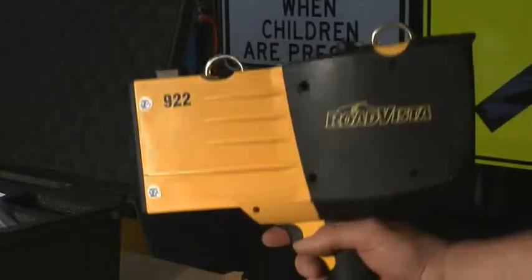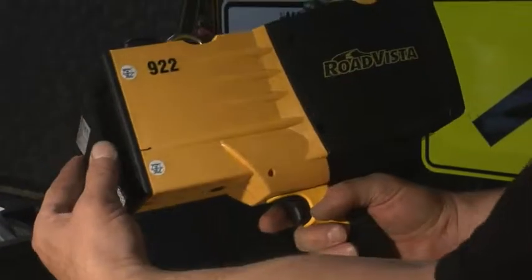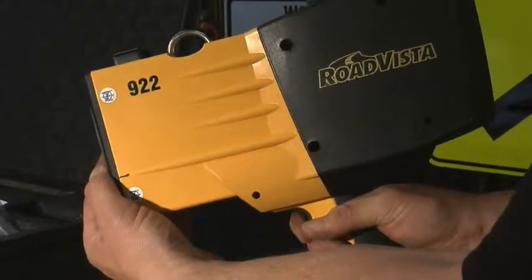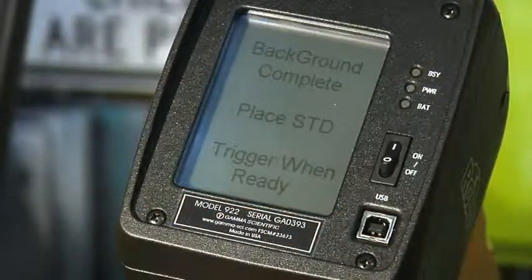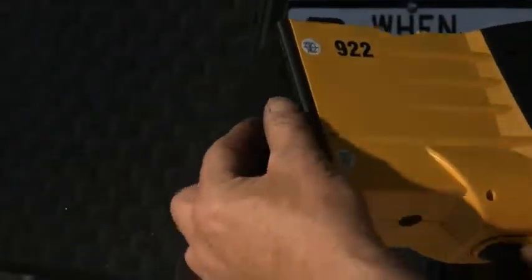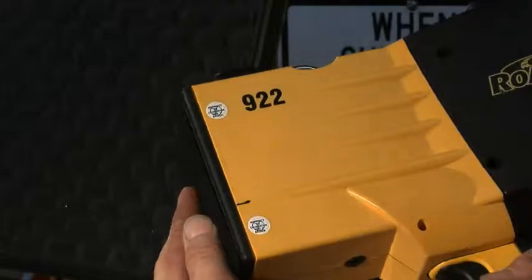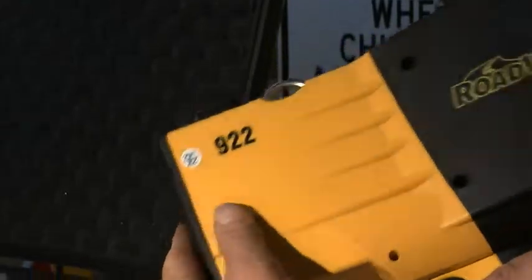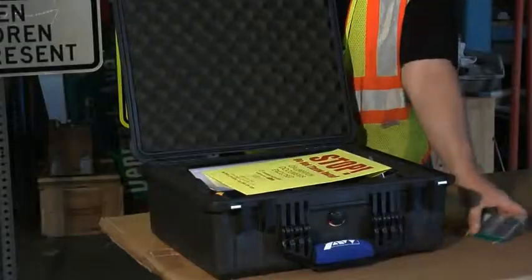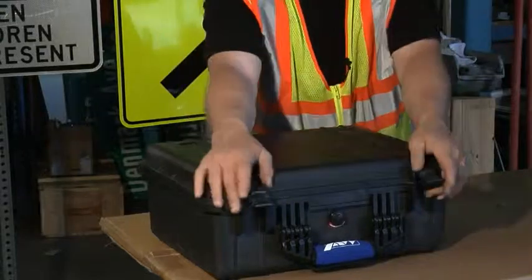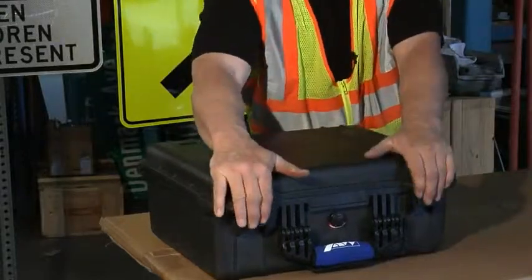Place the black or zero side of the calibration standard card over the trigger until a beep sounds. Repeat these steps using the reflective side of the standard to complete the calibration. Put the calibration standard back in its protective cover and store it in the carrying case. The device is now ready to collect data.